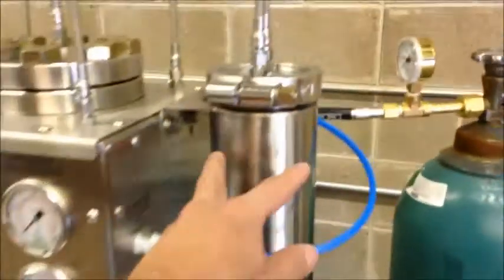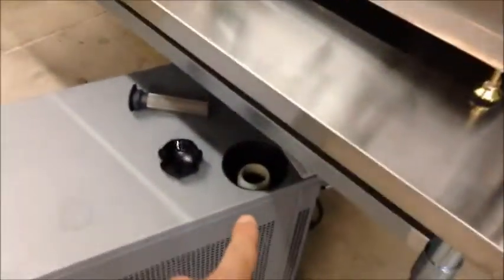First thing you want to do is fill your chiller full of water and propylene glycol. Right here, you'll fill it up. And once you think it's full, go ahead and leave your cap off, because when you turn this on and it starts filling up these jacketed vessels, your water level is going to lower and you're going to need to add more to it. Now you should be good to turn your chiller on.